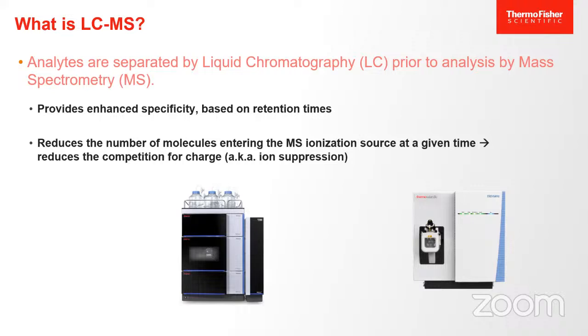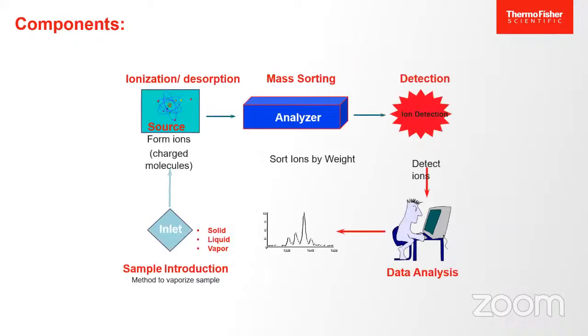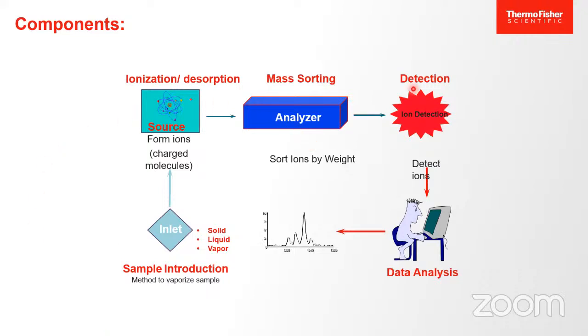That comes as sample prep. Coming to that, within the protein fraction, you want to separate different classes or types of protein so that you can identify them accurately. That is where the LC component comes into the picture. Before that, I just want to give you these schematics. Please keep in mind that this is the basic schematic of any mass spectrometer, irrespective of model or vendor. First, you have a sample inlet.